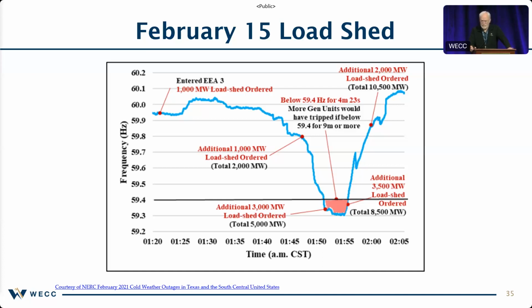At 59.4 hertz, they start a 9-minute timer on a protection system in ERCOT. If that 9-minute timer runs out, it trips off more generation. So in order to prevent that from happening, system operators call for 3,000 megawatts of load shed. A few minutes later, they call for an additional 3,500 megawatts of load shed. So still within our 45-minute period, we went from zero load shed to now 8,500 megawatts.